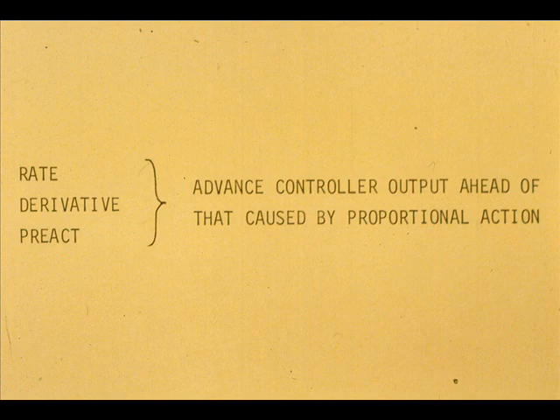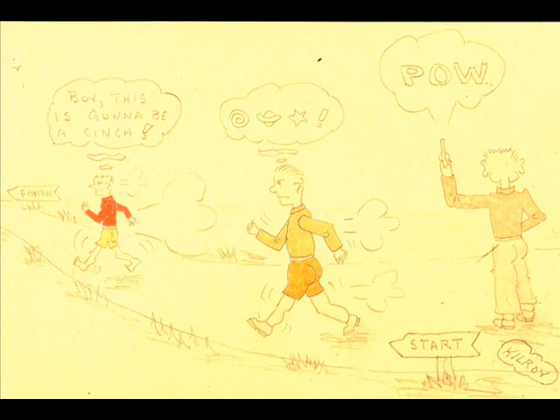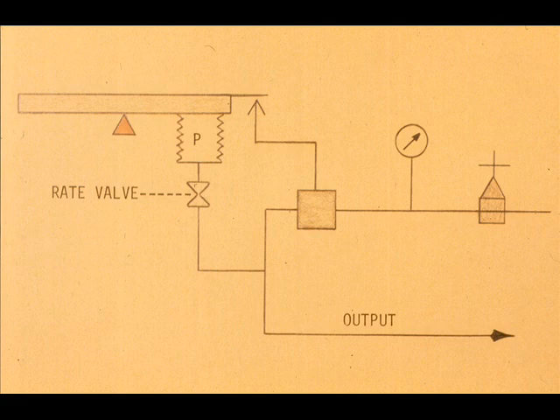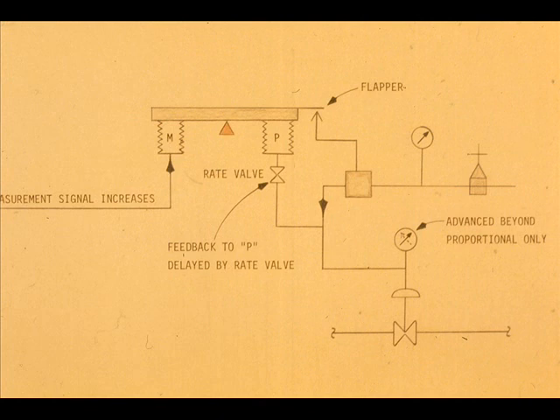These terms are synonymous. Rate, or derivative response, recognizes the speed at which the control point is leaving the set point. The reason being that the proportional output increases with distance from set point. Therefore, the rate valve is holding back an increasing amount of feedback to the proportional bellows. The output feedback into the proportional bellows is delayed, the nozzle stays nearer the flapper, and the output to the control valve is advanced.